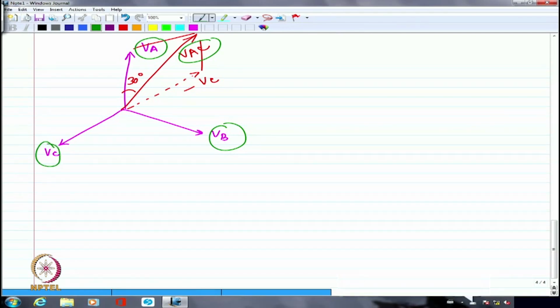If I am having primary as star, what I am applying is line to line voltage, and the line to line voltage on the delta side will be similar to the phase voltage. So not only is the voltage stepped down, but it is also shifted from the original line voltage by 30 degrees. So star-delta or delta-star configurations will always give a 30 degree phase shift between one side and the other.